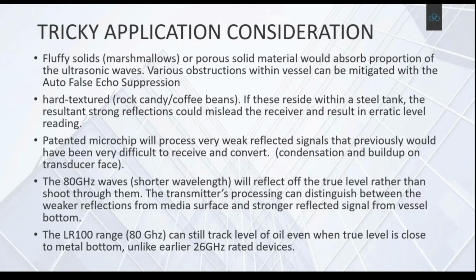It has happened with the old Milltronics, but Milltronics is a legacy enterprise in terms of ultrasonic level - it's been around for ages, and the technology still holds strong. What it brings, I know it sounds vague, but it's a patented microchip technology. So those signals that were either very weak or not too dissimilar to the signal that was emitted before it was reflected - these can now be processed, especially the weak signals. Previously they couldn't be registered by the transducer, but now they can. They meet a threshold, they can still be converted. This is why the LR100 will work in sort of tricky situations.